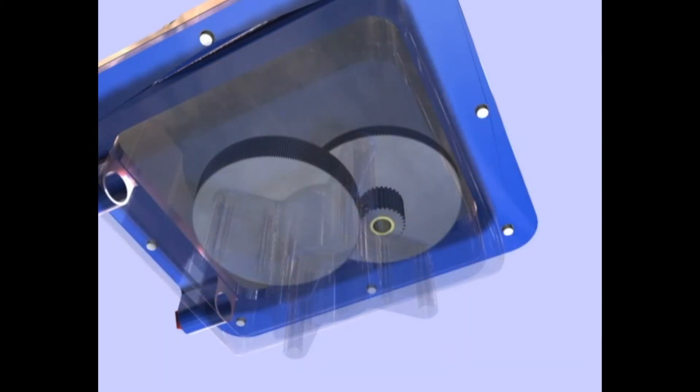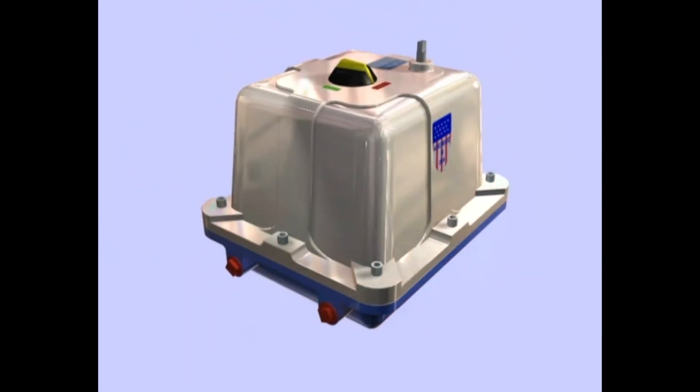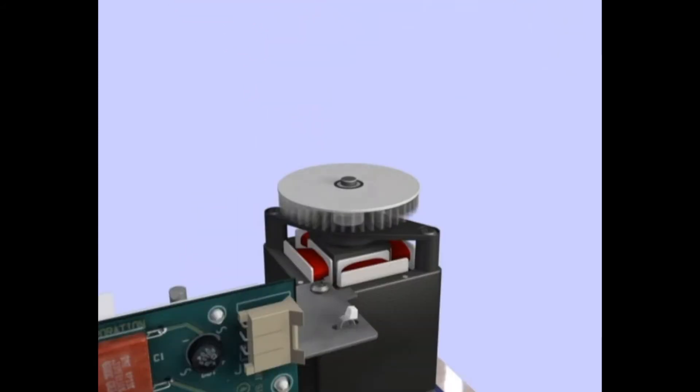The highly efficient, hardened steel spur gear train is permanently lubricated, providing output breakaway torque up to 3,000 inch-pounds and years of trouble-free performance. Under the cover, the standard fan-cool split-phased capacitor-run motor is conservatively rated for 75 percent duty cycle and can operate at either 50 or 60 hertz.